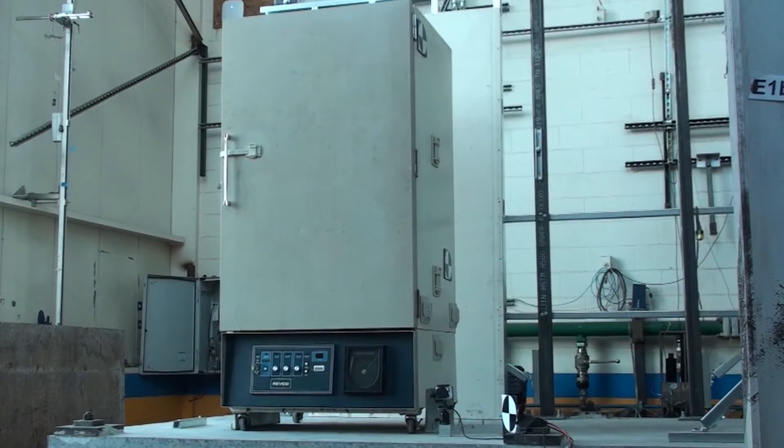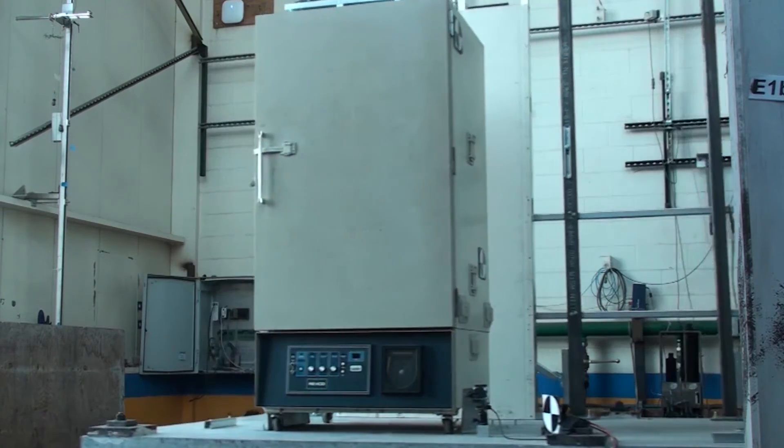I think we gained greater confidence in our building code requirements. Everything designed in accordance with the code performed well. Positions were retained, none of the units toppled or slid, thus there was no safety hazard in a large earthquake. And that should be very reassuring to all of us.